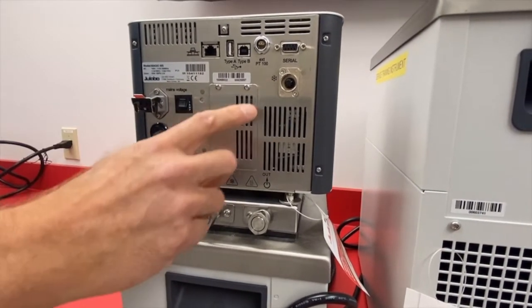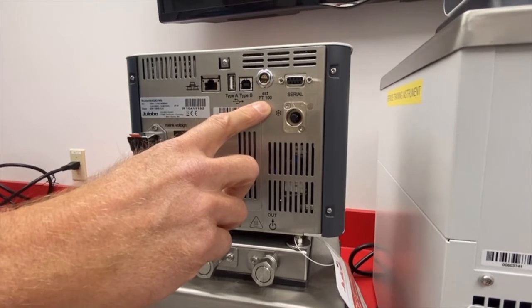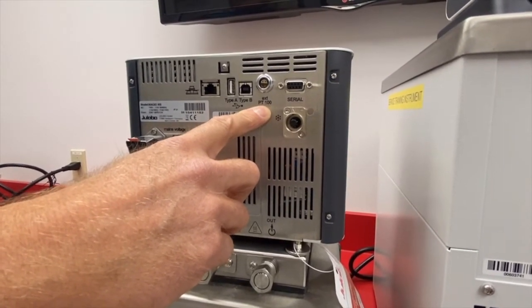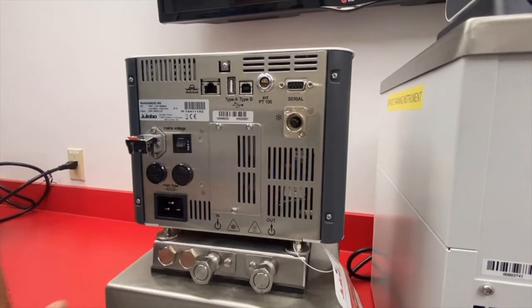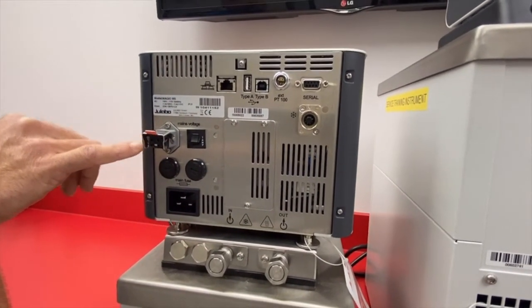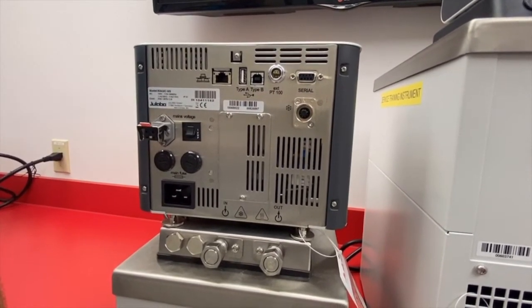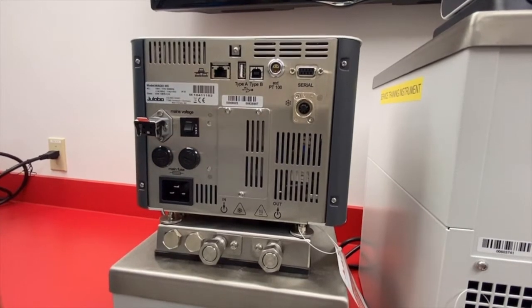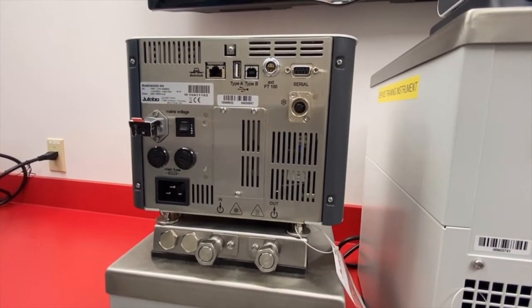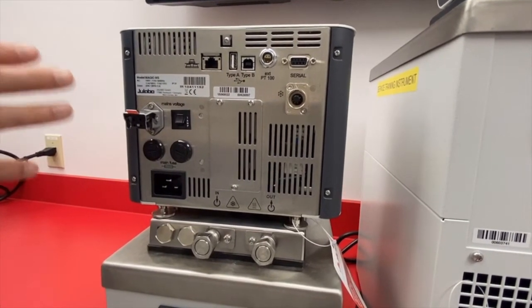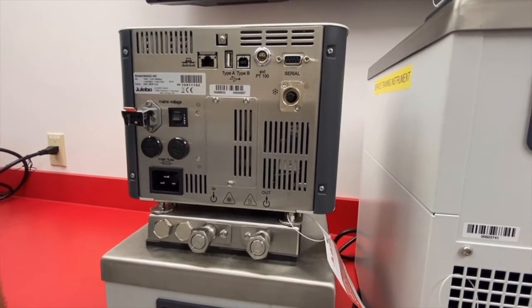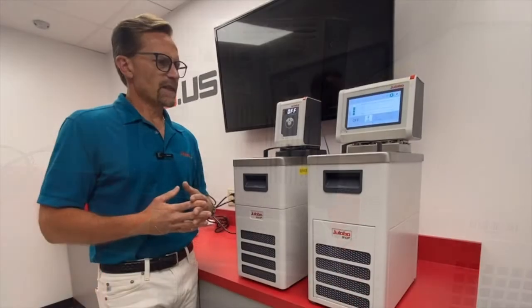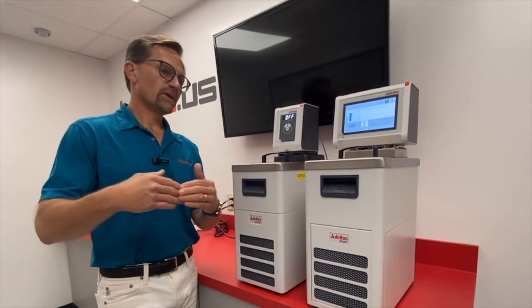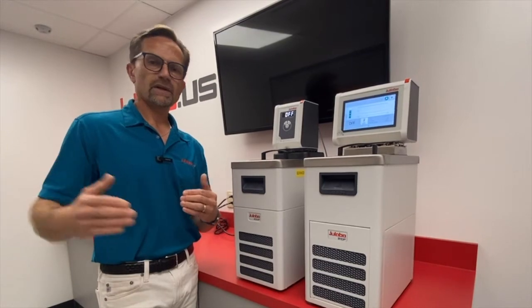Even more important for external temperature control, the MAGIO incorporates a port for external PT100 sensors, enabling you to control from the position of that sensor. And the MAGIO also incorporates a socket output. This is a voltage, either 115 or 230 volt depending on which unit you have, to control external devices like solenoid valves or cooling water valves. So you can see that the MAGIO has a lot more to offer as far as modern communication and interfacing. Also, the MAGIO has 1, 2, and 10-point calibration. So if you are running an application across a broad temperature range and you really want to do a fine-tuned calibration curve, you can do so with the MAGIO.